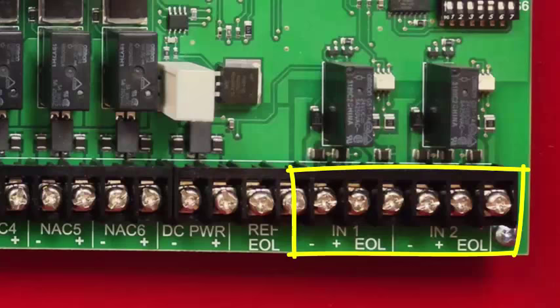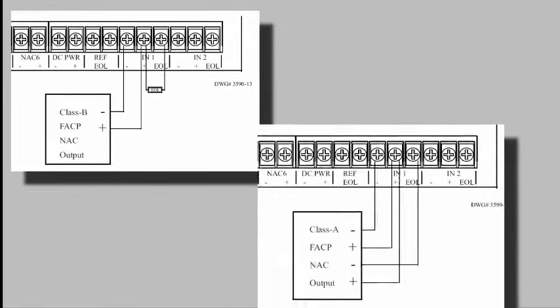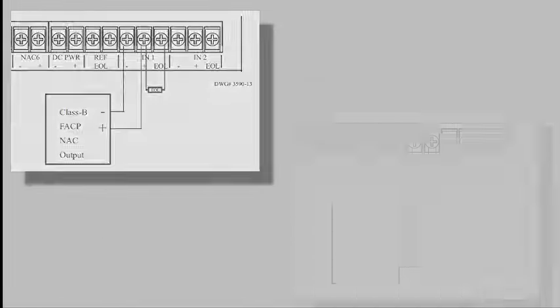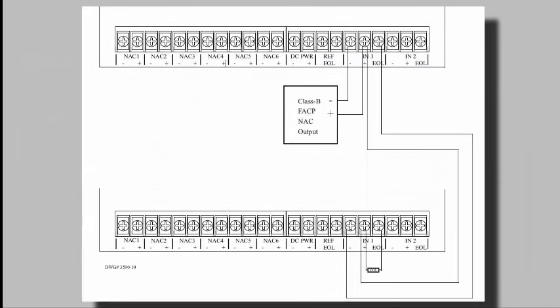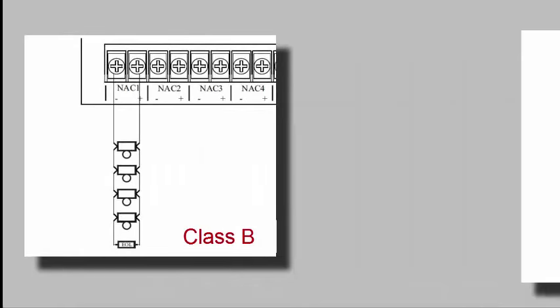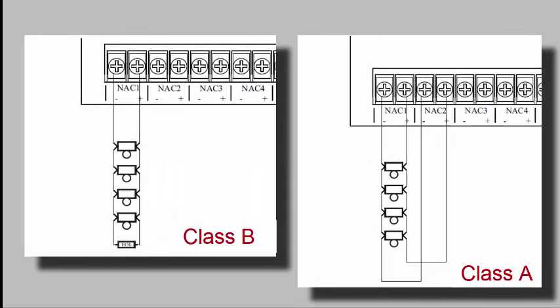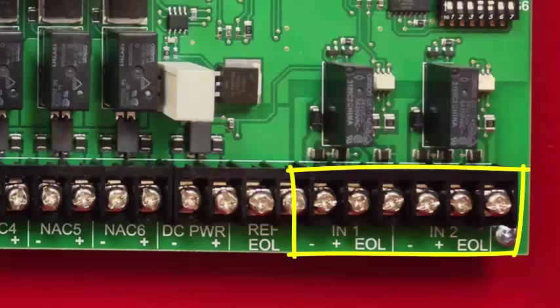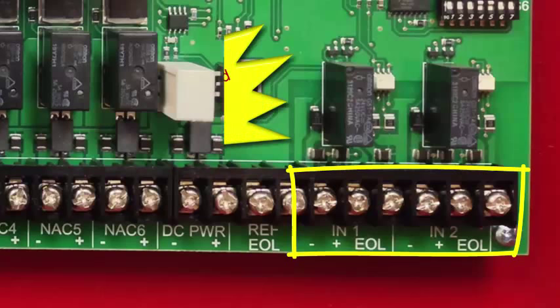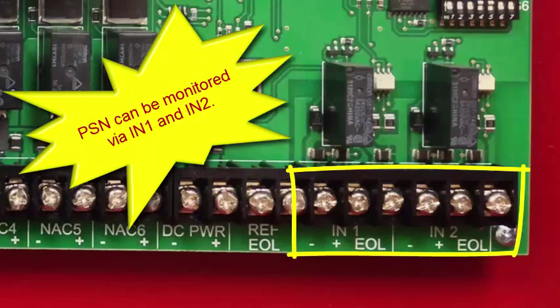Input one and two can be connected to a class B or class A trigger circuit as seen here. Multiple power supplies can be triggered by the same circuit. Remember to install an end-of-line resistor at the last power supply. Each NAC output circuit is individually selectable for class A or B operation. This is done through the dip switch programming. Another thing to note about the two input triggers is that they have built-in trouble monitoring relays, which means that supervision of this power supply can be accomplished through the trigger inputs and there is no need to monitor the dedicated trouble contact.